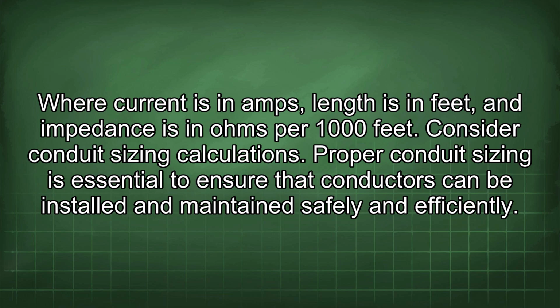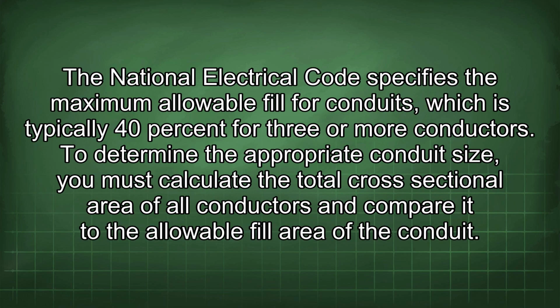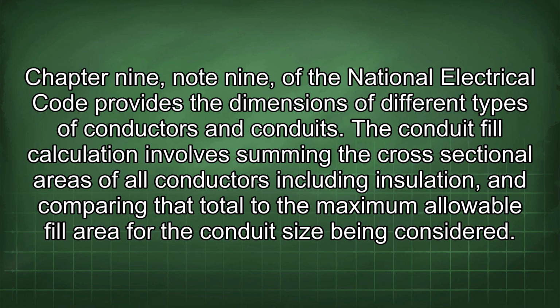Consider conduit sizing calculations. Proper conduit sizing is essential to ensure that conductors can be installed and maintained safely and efficiently. The National Electrical Code specifies the maximum allowable fill for conduits, which is typically 40% for 3 or more conductors. To determine the appropriate conduit size, you must calculate the total cross-sectional area of all conductors and compare it to the allowable fill area of the conduit. Chapter 9, Note 9 of the National Electrical Code provides the dimensions of different types of conductors and conduits.